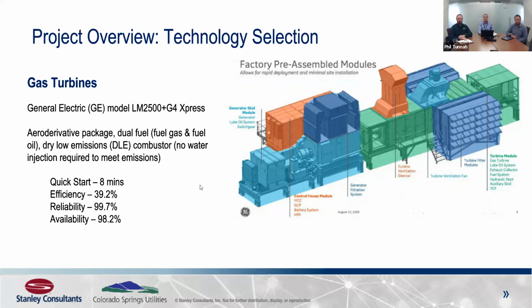These are aeroderivative packages, and in this case, for our site, we did dual fuel — both natural gas and fuel oil, with fuel oil being the backup, not primary. This unit had a dry low emissions (DLE) combustor, which allowed it to avoid water injection to meet its emissions targets and guarantees.